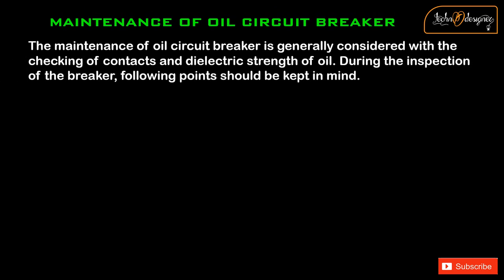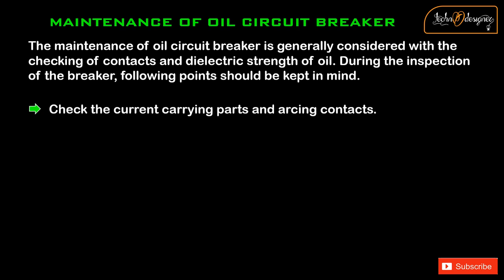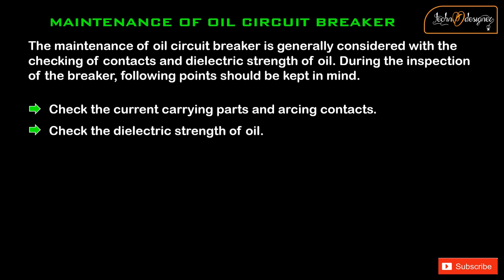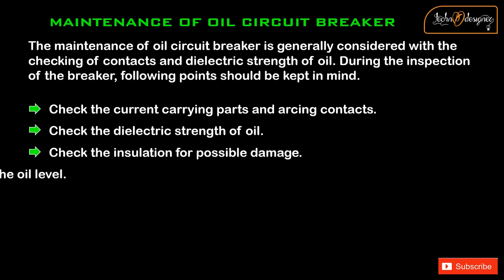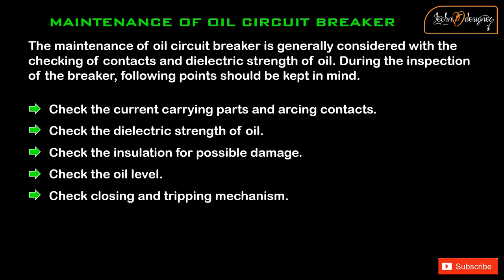Maintenance of oil circuit breaker: Maintenance is generally concerned with checking the contacts and the dielectric strength of oil. During inspection, the following points should be kept in mind: check the current carrying parts and arcing contacts, check the dielectric strength of oil, check the insulation for possible damage, check the oil level, and check the closing and tripping mechanism.